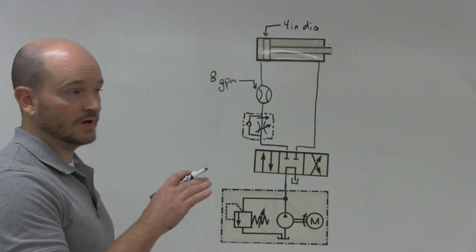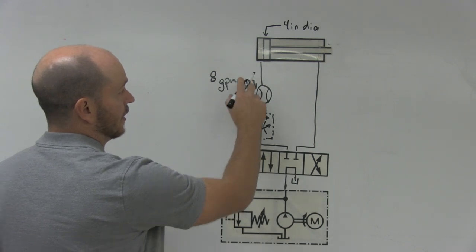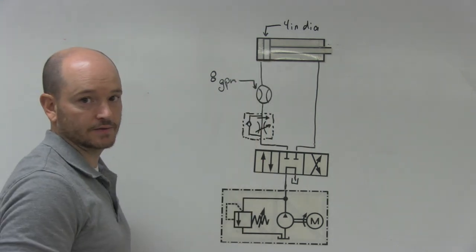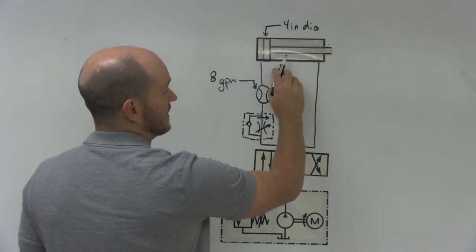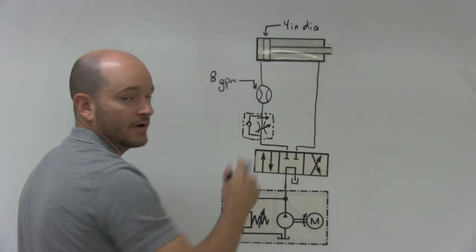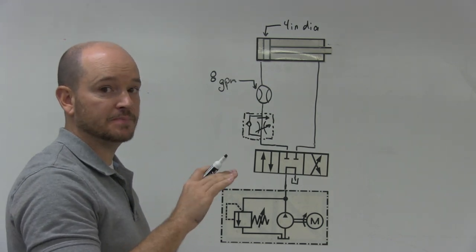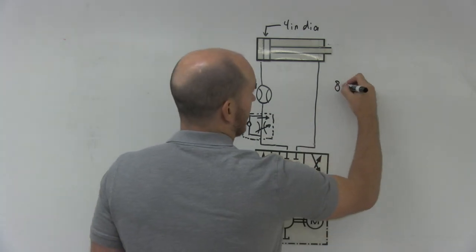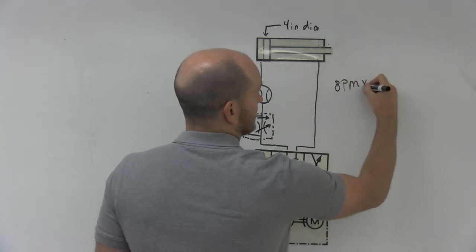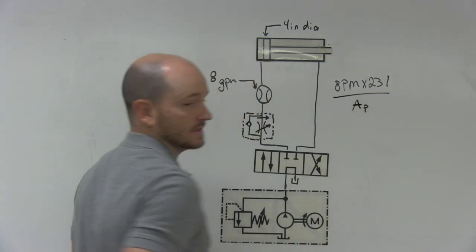So in this video we're going to assume that we have 8 gallons per minute being read here going into the cylinder, and we have a 4 inch diameter piston on the cylinder that we are attempting to control. So the formula to calculate out the speed in inches per minute is gallons per minute times 231 divided by the area of the piston.